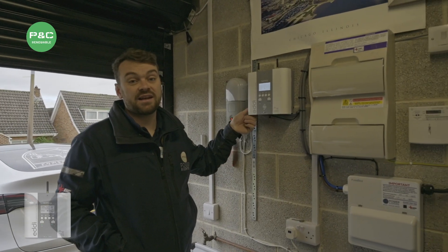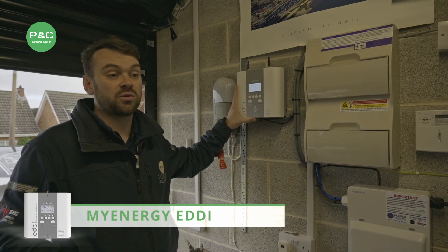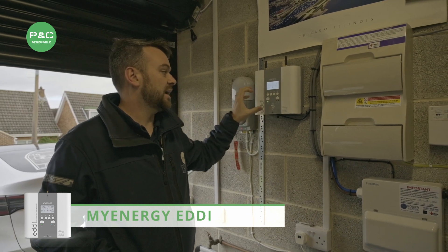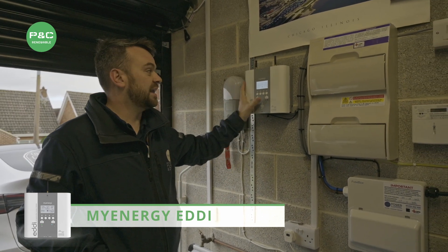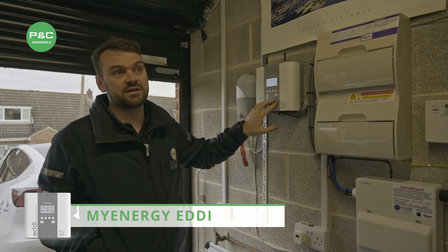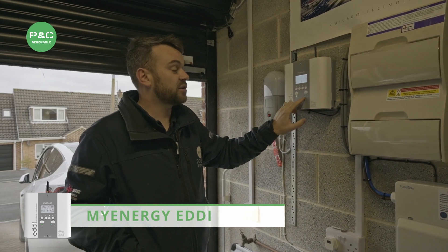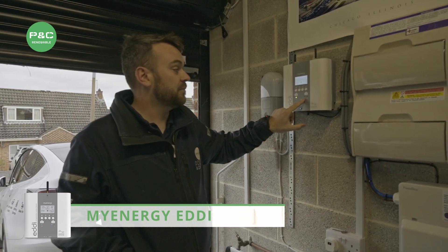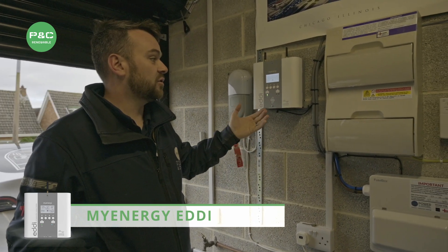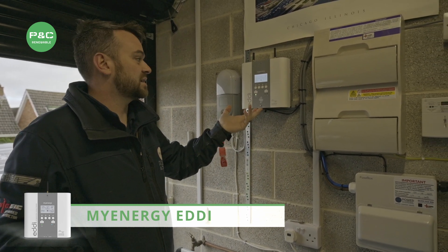This is a MyEnergy Eddi — it's a hot water diverter. It will pick up all the surplus solar, so anything you'd usually send back to the grid, before it goes back it will choose whether to heat up your immersion heater tank. The one we've got here has two immersion heater elements connected to it: it will do the first element and once that's up to temperature it will switch to the second. Once both are done it will send the remainder back to the grid, but you've made the most out of your excess energy.